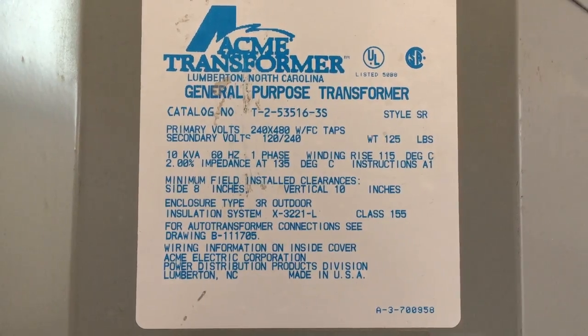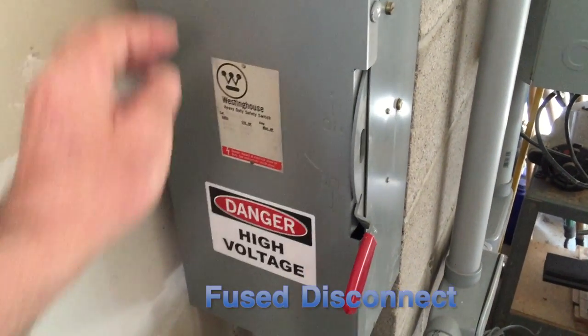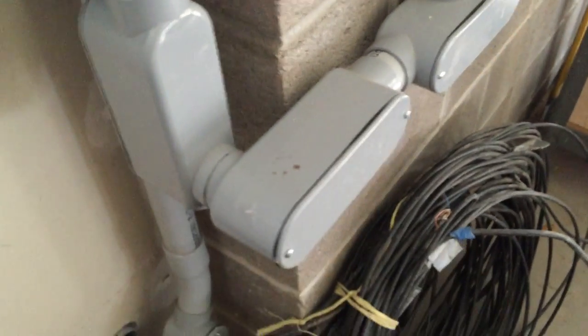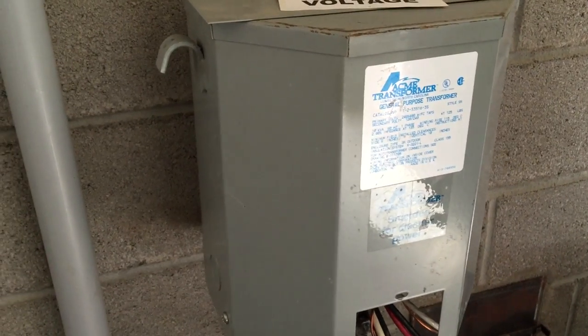The tradeoff is that we will need a 480 volt transformer at the house to step the power down. To prevent tampering, we have placed the fuse disconnect inside the garage. The two hot legs of the 480 volt go through fuses and then into the primary side of the 10 kVA single-phase transformer. This transformer is wall mounted on concrete block in hopes that any vibration will not transmit as sound into the living space.